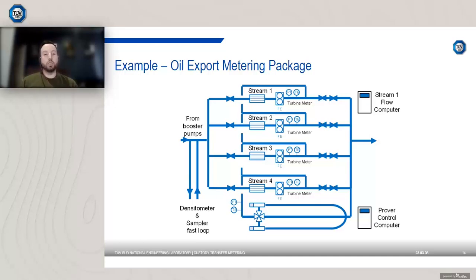So this is just an example of a typical oil export metering package. It's a 4-stream system. Each stream here has a flow measurement device, in this case a turbine meter. Each has a pressure and temperature measurement. Each has a flow conditioner, which is quite important in most cases for turbine meters.